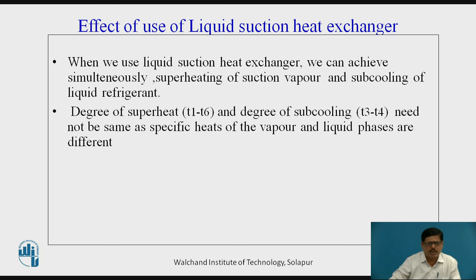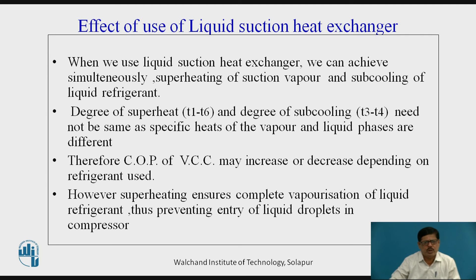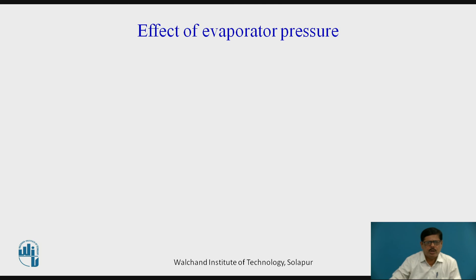In practice, we can simultaneously achieve superheating of suction vapor and subcooling of liquid refrigerant by using the liquid suction heat exchanger. An important point to note is that the degree of superheat — T1 minus T6 — and the degree of subcooling — T3 minus T4 — need not be the same, because the specific heat of vapor and liquid phases are different. Therefore, the COP of the vapor compression cycle may increase or decrease depending on the refrigerant used. However, superheating ensures complete vaporization of liquid refrigerant, thus preventing any entry of liquid droplets into the compressor.